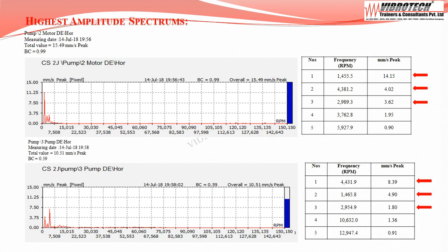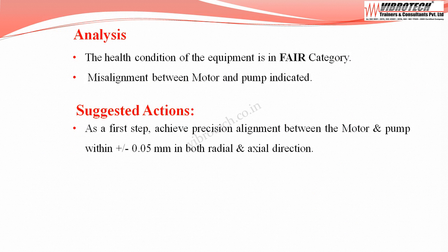Going through the spectrum and frequencies, at the motor drive end the dominant peak frequencies are 1×, 2×, and 3× the running RPM, indicating misalignment between the motor and pump. Spectrums at the pump drive side also show dominant peak frequencies of 1×, 2×, and 3× running RPM, which also indicates misalignment between the motor and pump. The equipment is analyzed to have misalignment between motor and pump.